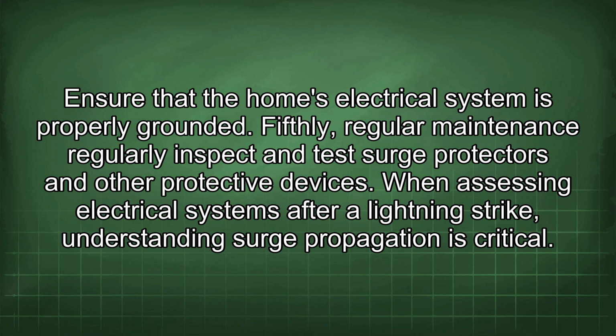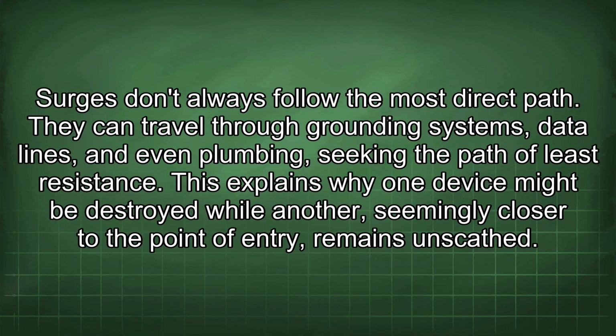When assessing electrical systems after a lightning strike, understanding surge propagation is critical. Surges don't always follow the most direct path. They can travel through grounding systems, data lines, and even plumbing, seeking the path of least resistance. This explains why one device might be destroyed while another, seemingly closer to the point of entry, remains unscathed.